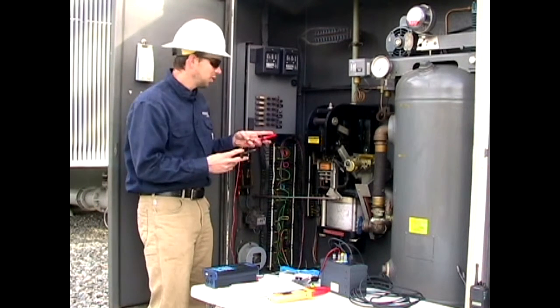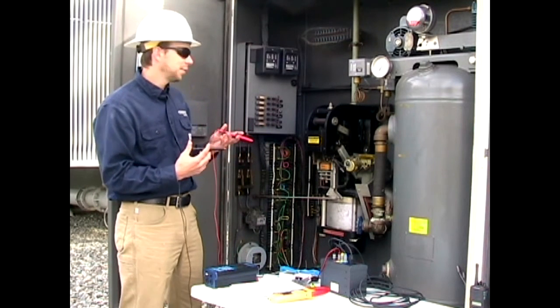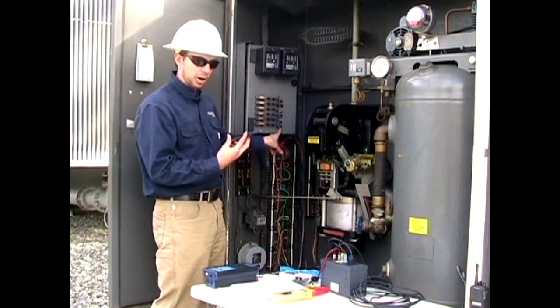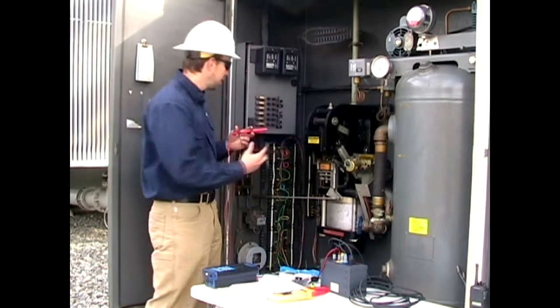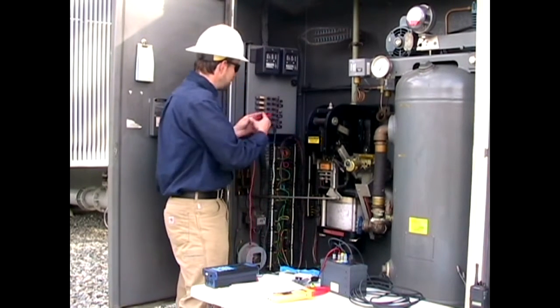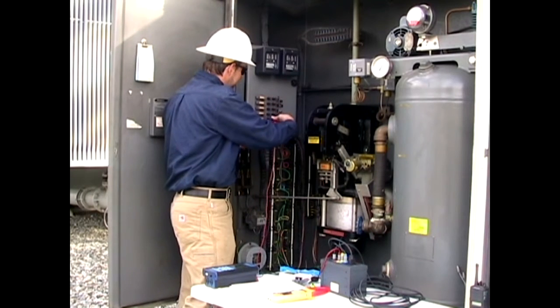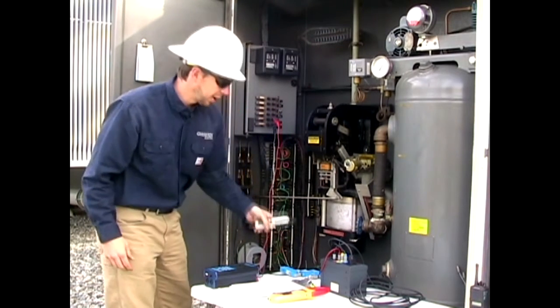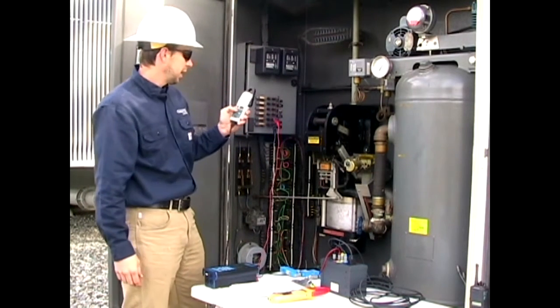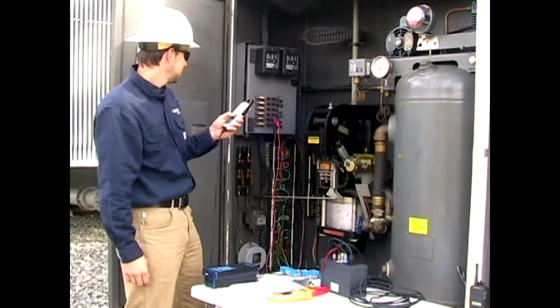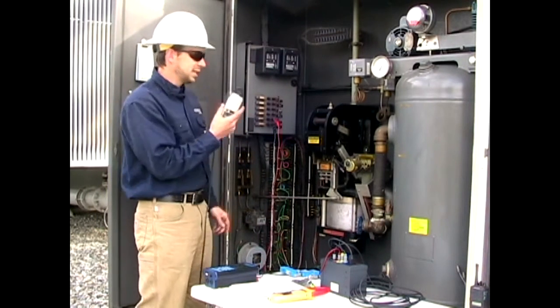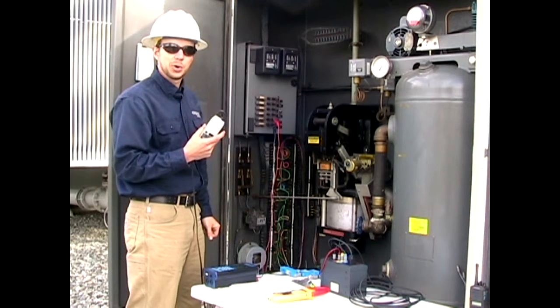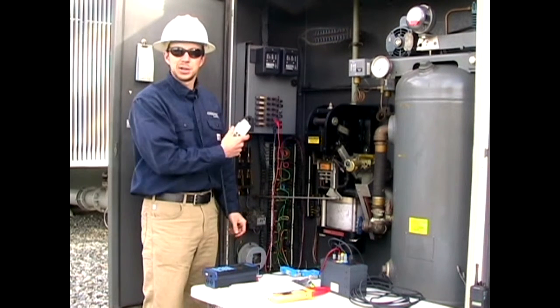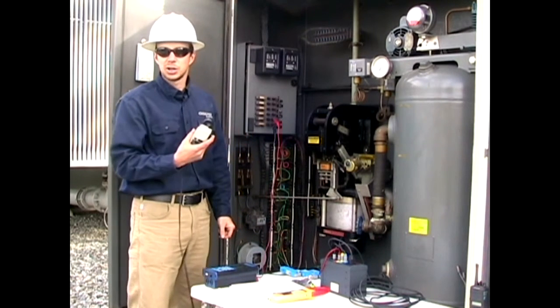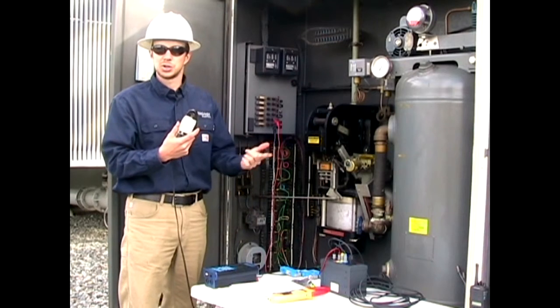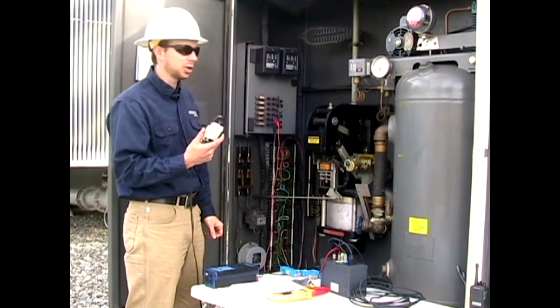Now, first thing we got to do is our DC supply, your positive and negative. So we verified here on our control that the negative is on the bottom. So there's our negative lead, here's our positive lead. Then we got to put our amp probe on, and our amp probe should be turned on to 20 amps. And this has to go on the wire that's going to lead to our trip coil. So when you're catching a trip, you'll put this on the wire that leads to your trip coil. If you're catching a close, this will be on the wire that goes to your close coil, and it has to be in series because you need to monitor all the current.